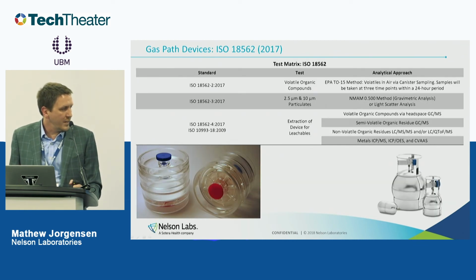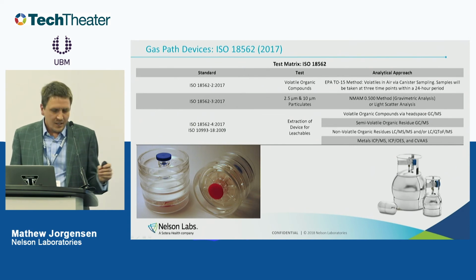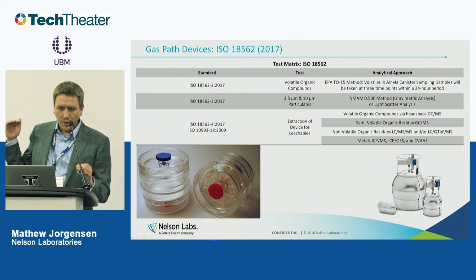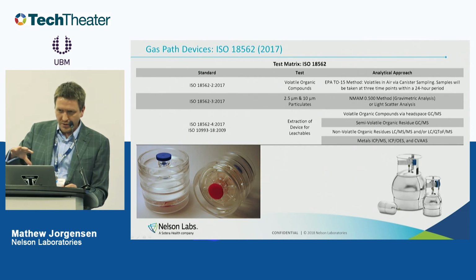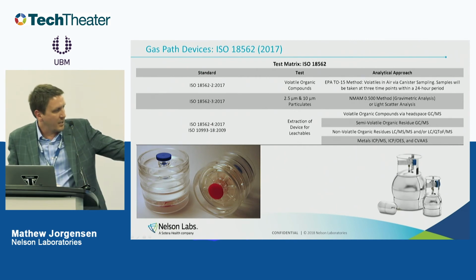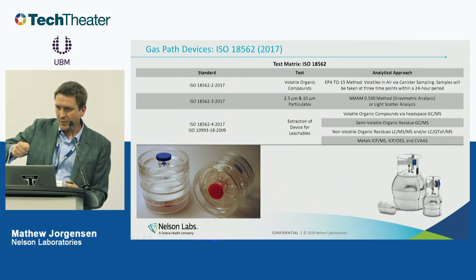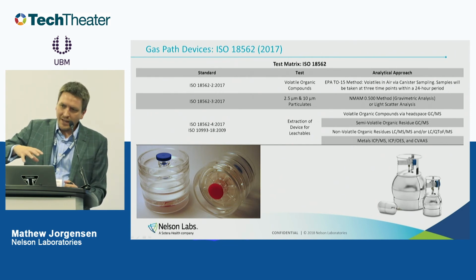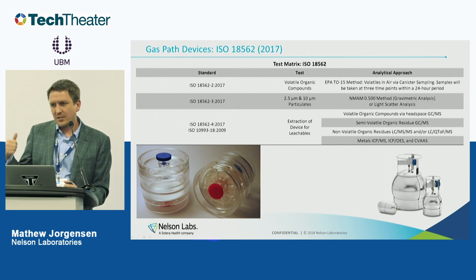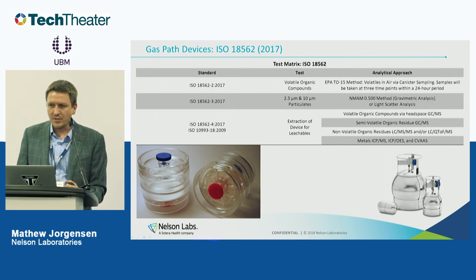The way that we run this, something that we have running inside Nelson Labs now, is to measure the volatiles. We direct clean filtered air through the device in a controlled environment. Then we use one of these vacuum canisters to sample the gas over a period of time. And then we can pump everything out of the canister into a GCMS and analyze what's there that way.